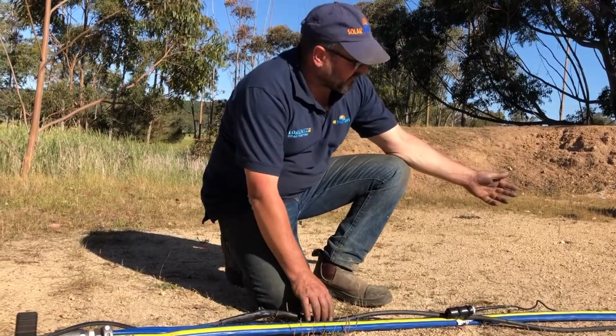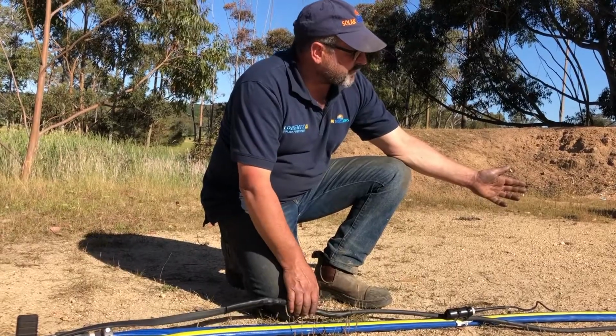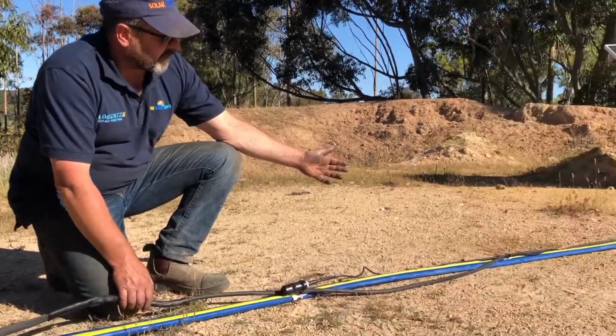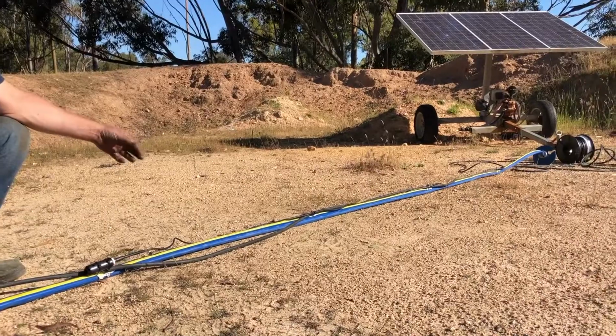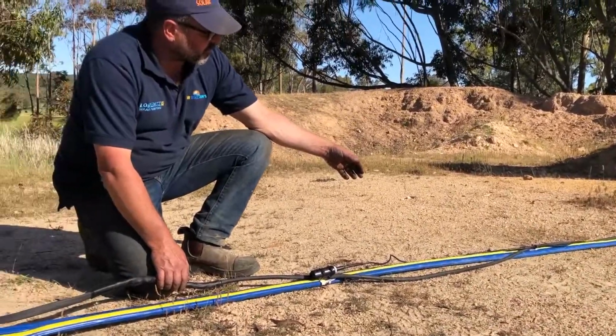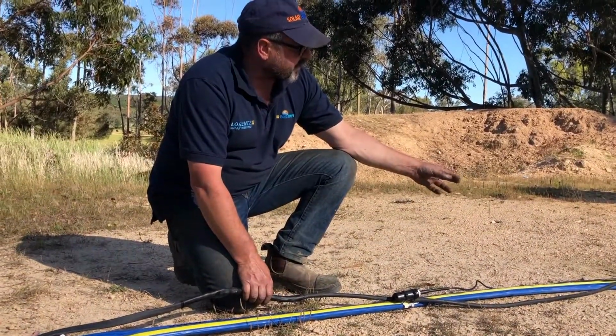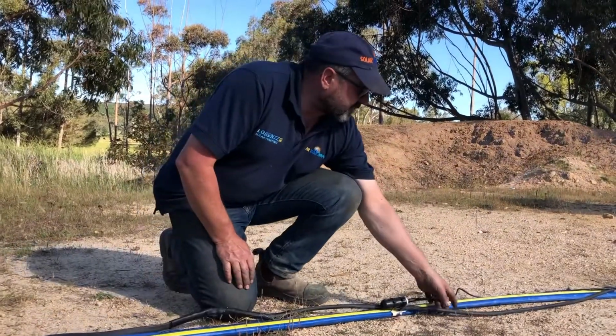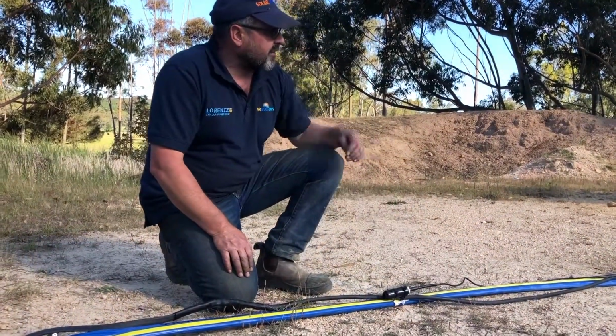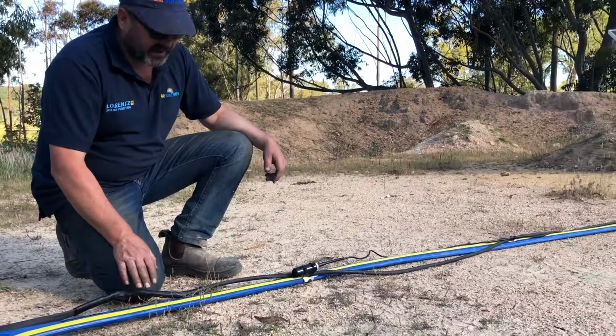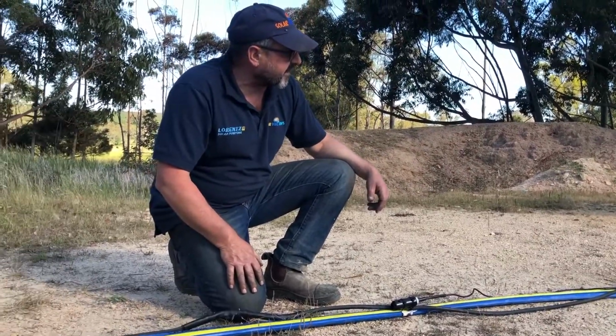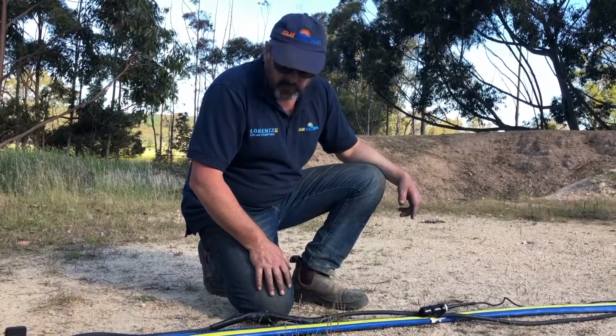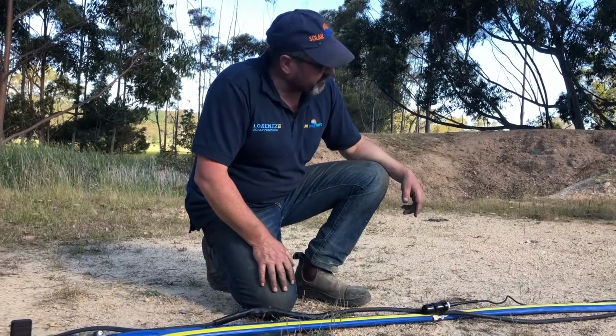As you can see with the Crusader Flexibore, we've got cable ties every metre, and I insist on using rated cable ties. Each cable tie is rated at 22.2 kilograms minimum strength, and we've got the electrical drop cable longer than the Crusader Flexibore, just to allow for any stretch or movement in the Flexibore. It's a really robust system and it's easy to install yourself.